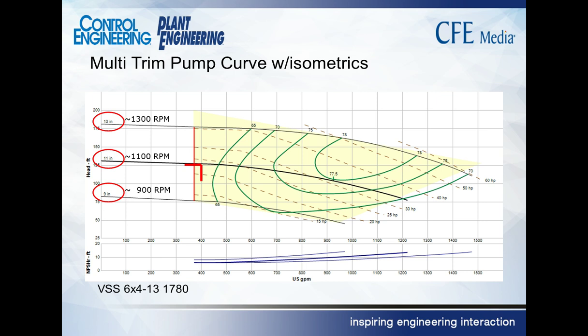Because on this one it's got a dashed line. The green lines are the same. That's the efficiency, isometric. The little dashed brown lines are the power. And if you look as it moves from the upper right to the lower left, the power goes down. So this is also isometric, and it's like walking down the mountain. As you come down, you can see that your power drops. So the operating point in this case is somewhere, I can't read that slide. It's too small on my screen. You can probably see it on yours. It looks like it's between 25 and 20 horsepower. Is that correct? A little closer to the 25, so maybe 22 horsepower. Okay. Hope that answered that question.